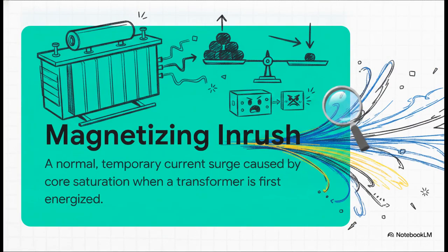Well, the answer is something called magnetizing inrush. This is a completely normal, temporary current surge. It happens because the transformer's magnetic core briefly saturates when it's first woken up. Get this. This inrush current can actually be several times higher than the transformer's normal full-load rated current. If our relay were just a blindly sensitive balance scale, it would misinterpret every single routine startup as a deadly fault. It would just trip immediately, causing constant, incredibly frustrating nuisance trips.